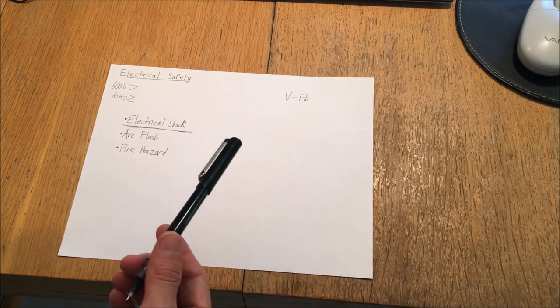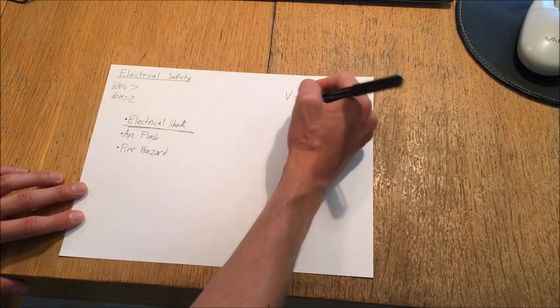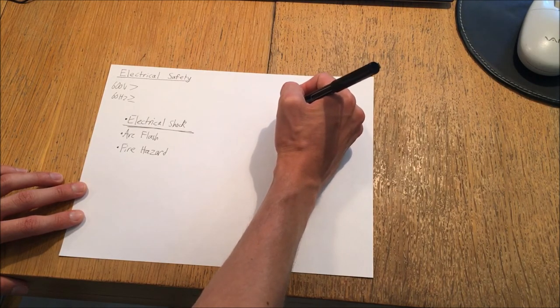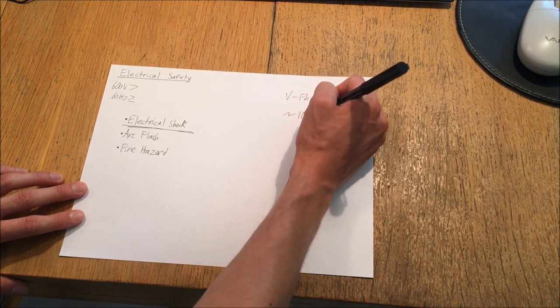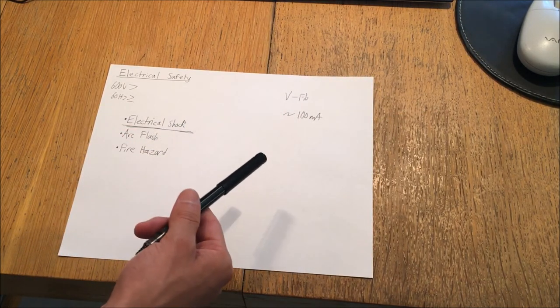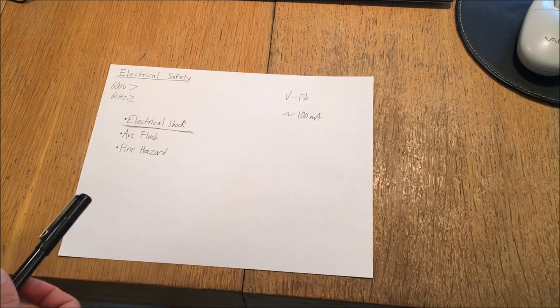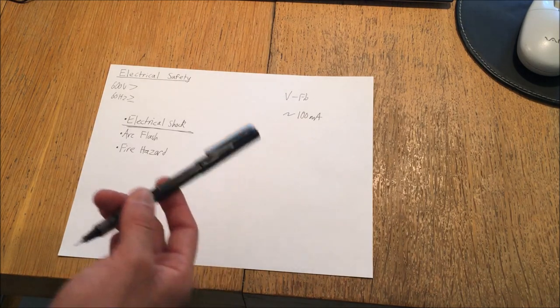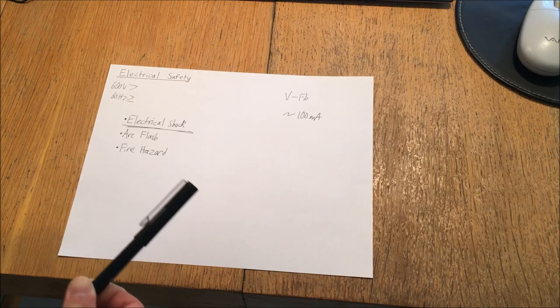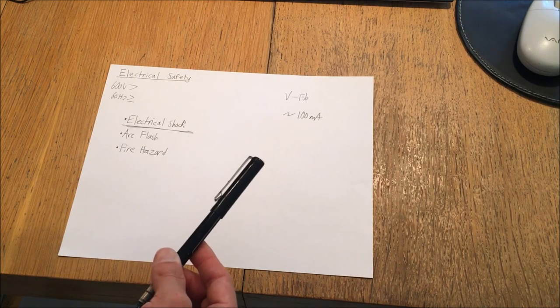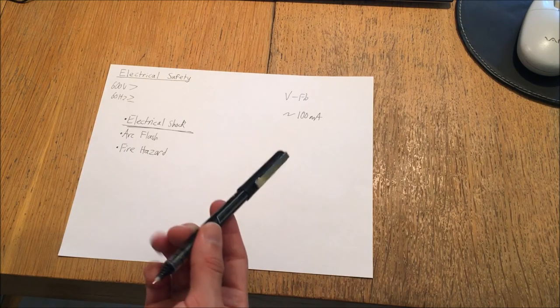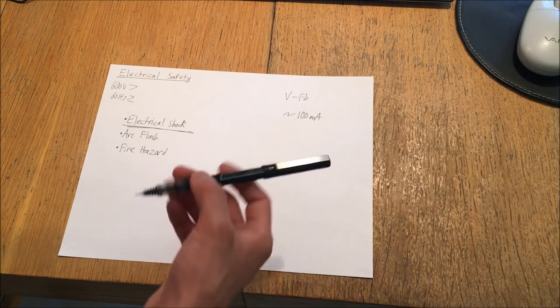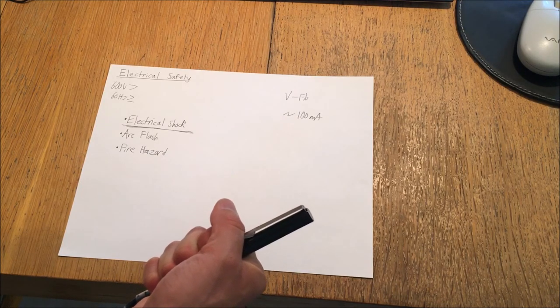This occurs when the arm-to-arm current, that is roughly the current from one hand to the next, is approximately 100 milliamps or greater. This can also occur with less current than 100 milliamps, anywhere down to around 50 milliamps can be harmful. There are other conditions which can also lead to hazards where relatively low currents cause you to clench onto what you're working on and not be able to let go.